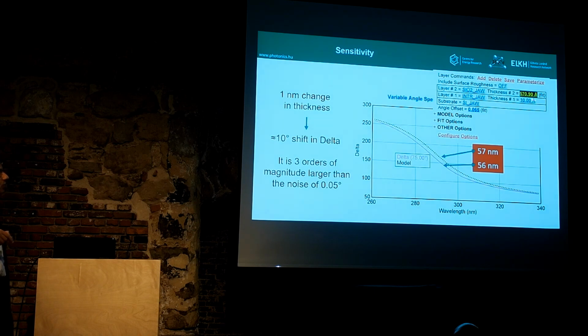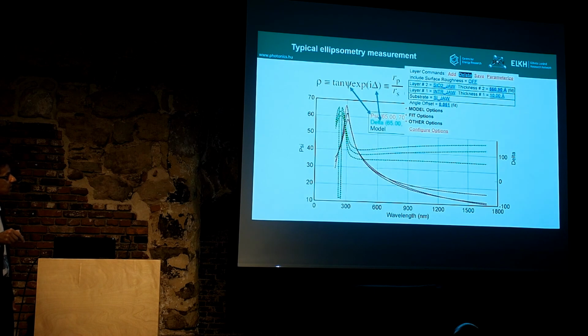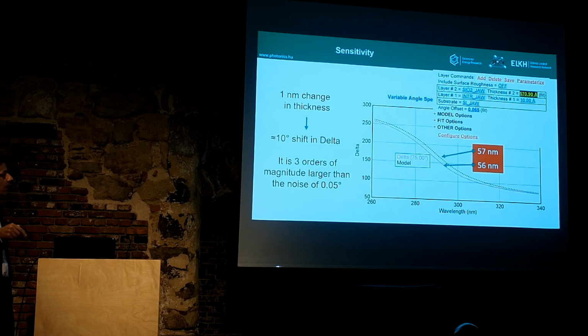But what if we change the thickness? Here it's 56 nanometers, and we change it to 57 nanometers, an increase of 1 nanometer. Focusing on delta, the phase shift, the black line is the simulation for 57 nanometers and the purple is for 56. So changing 1 nanometer in thickness changes the delta value we measure by approximately 10 degrees.